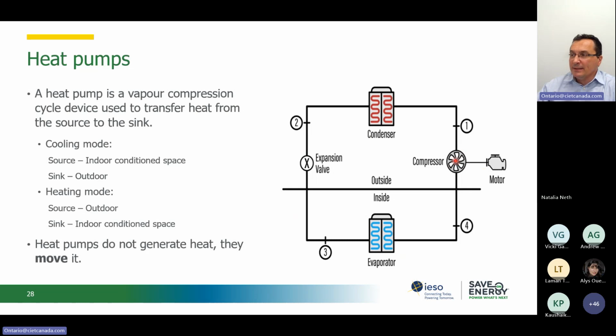And with the compressor, we are now increasing the pressure. So if we draw now a horizontal line between the expansion valve and the compressor, anything we have above the line would be high pressure, and anything we have below the line would be low pressure. So we control the pressure here, and this will allow us to condense the refrigerant that flows through this pipe system at a temperature where the condenser will reject the heat, and then will evaporate the refrigerant in the evaporator by absorbing heat from where we want this heat to come from. So we basically have a source of heat where the evaporator absorbs the heat, and then we have a sink where the condenser dumps this heat.